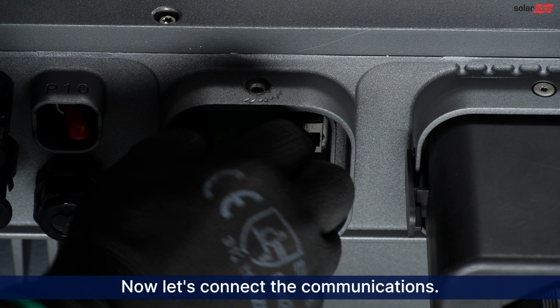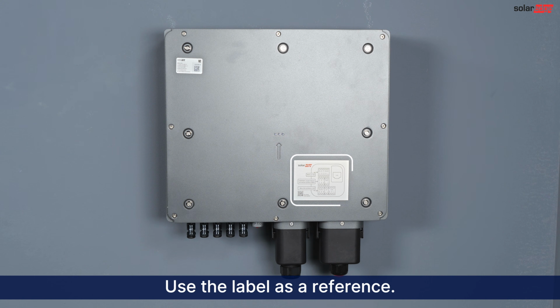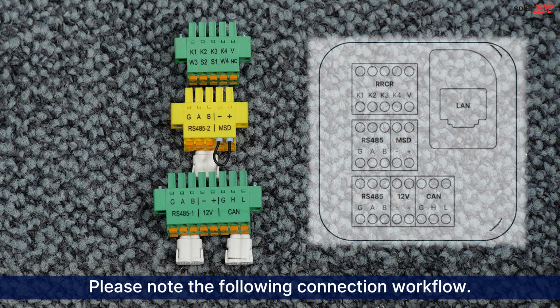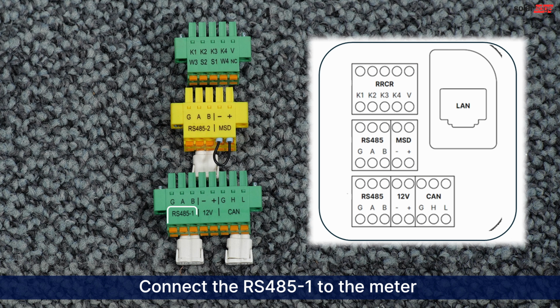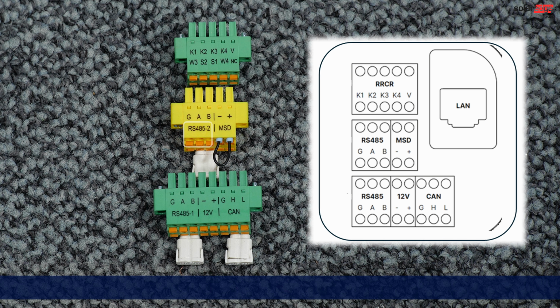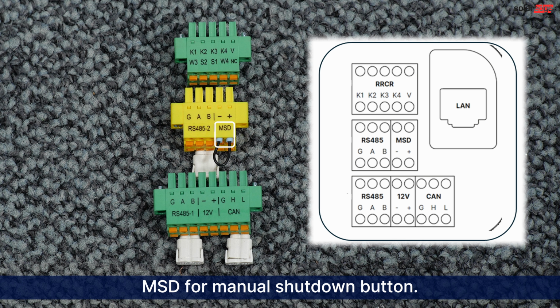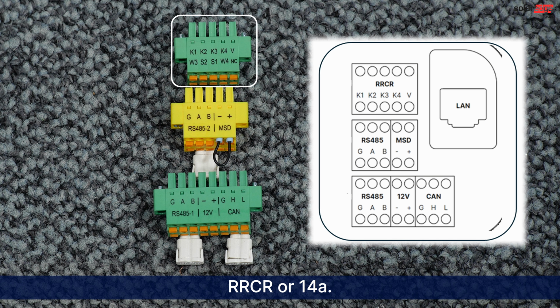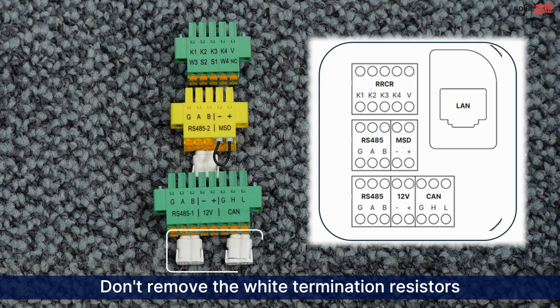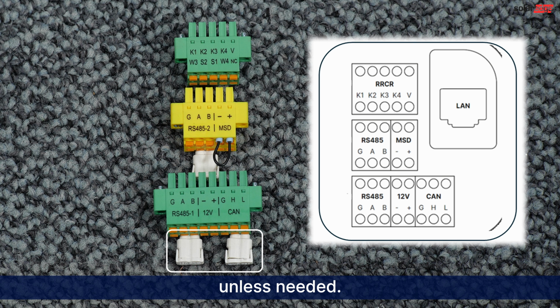Now let's connect the communications. Use the label as a reference. Please note the following connection workflow. Connect the RS485-1 to the meter or backup interface, the 12-volt for the backup interface, CAN for battery, CAN or RS485-2 for multi-inverter, MSD for manual shutdown button, RRCR or 14A. Don't remove the white termination resistors unless needed.